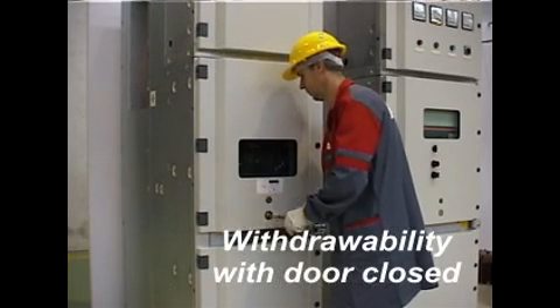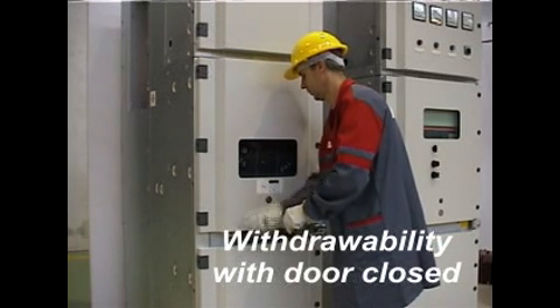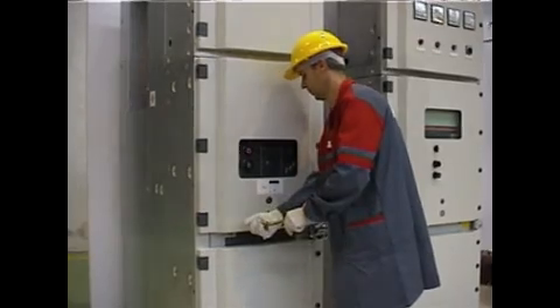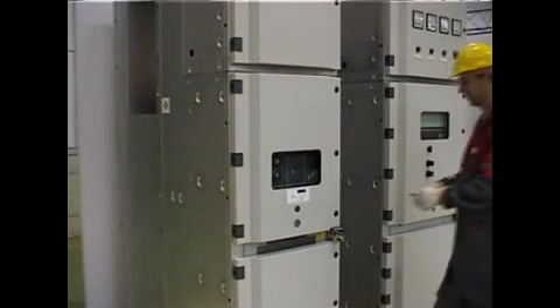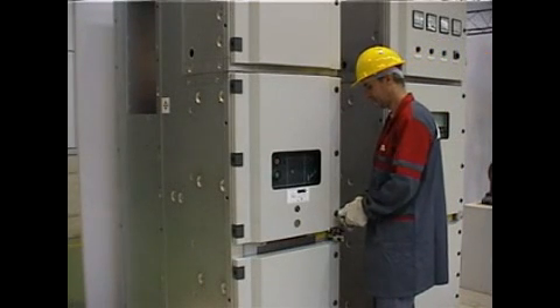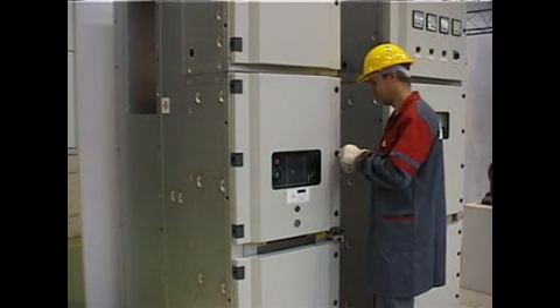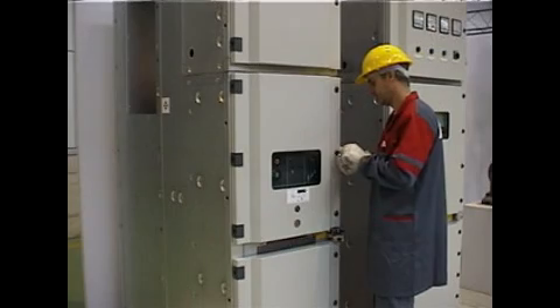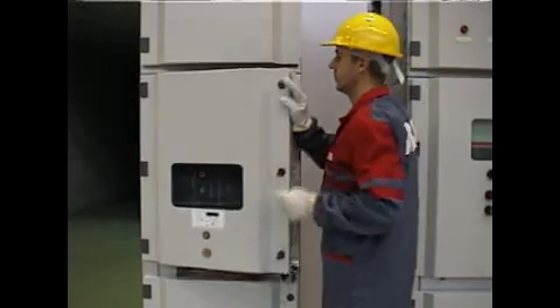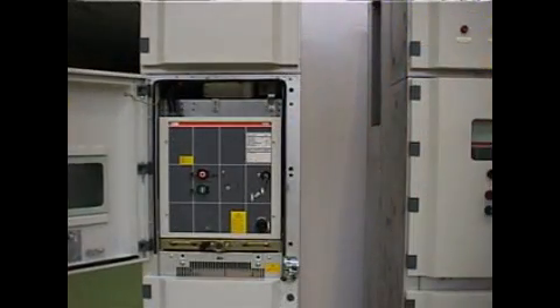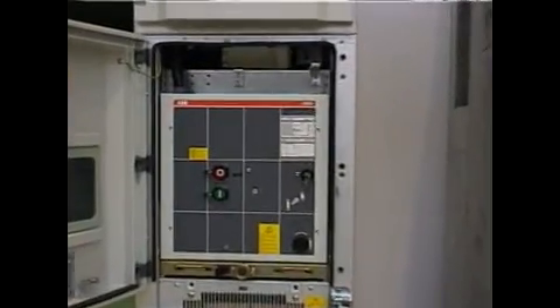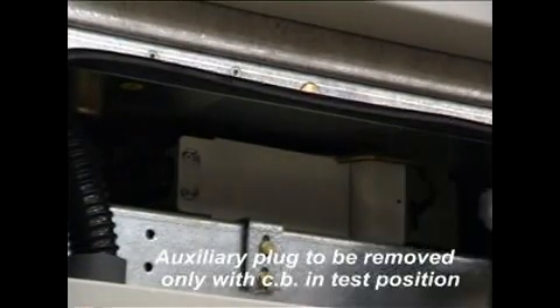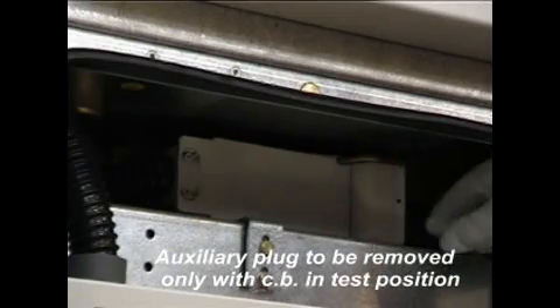At this point, the circuit breaker can be safely withdrawn in test position, and we will have the possibility to open the door. When the door is completely opened, we have a direct view of the circuit breaker operating mechanism with the auxiliary plug on the top still connected to the switchboard. We can notice the interlock which prevents the auxiliary plug from being removed when the circuit breaker is not in fully withdrawn position.